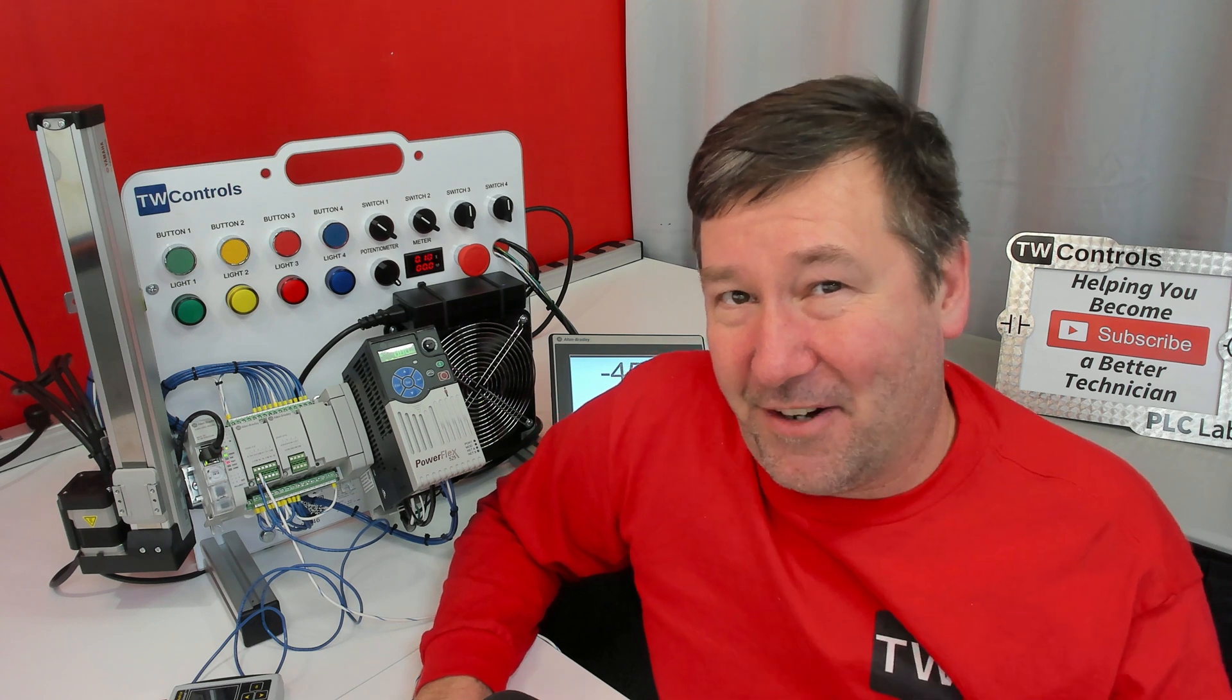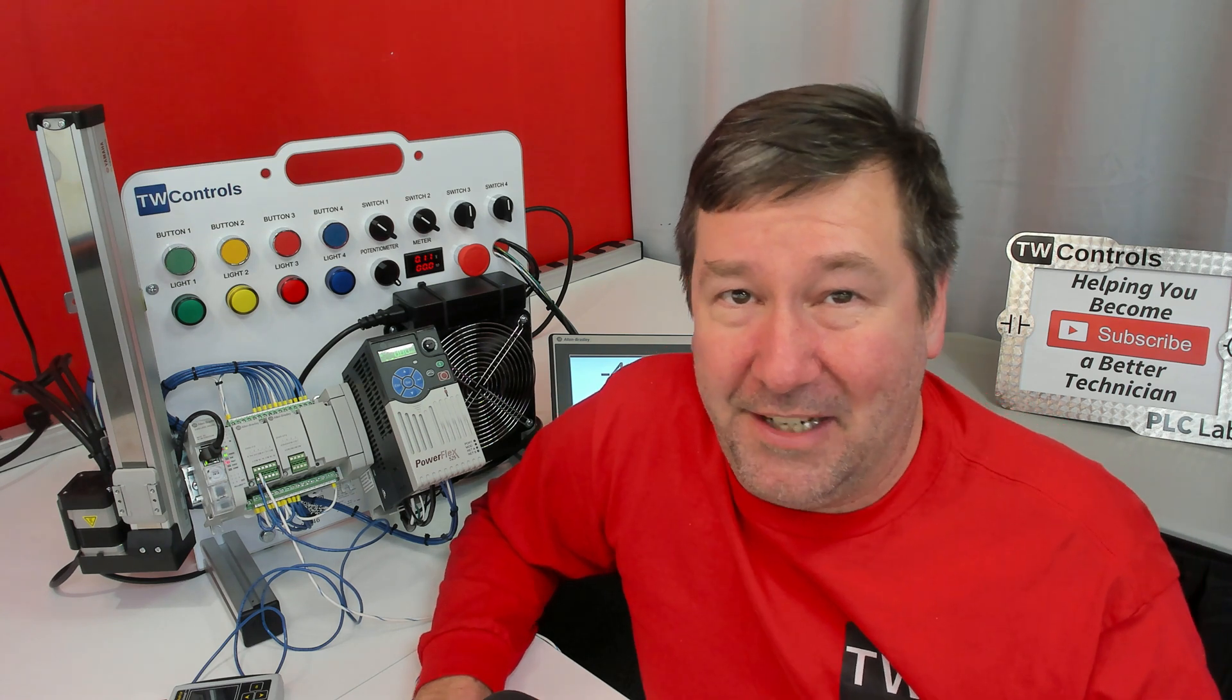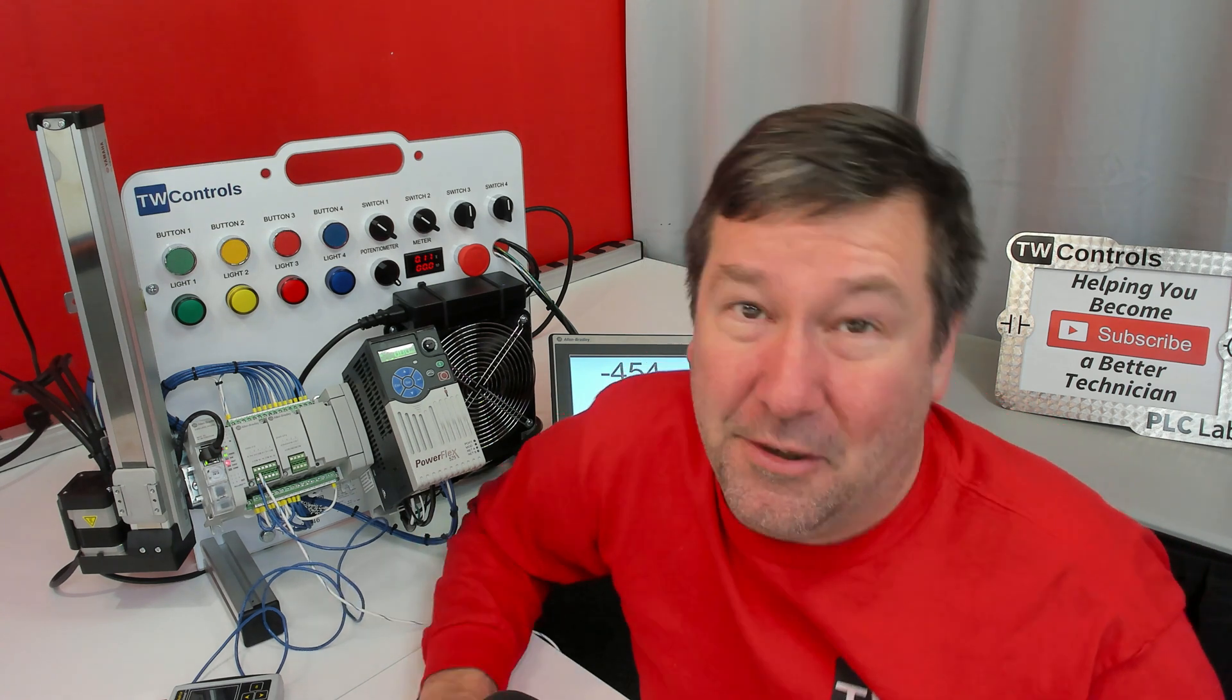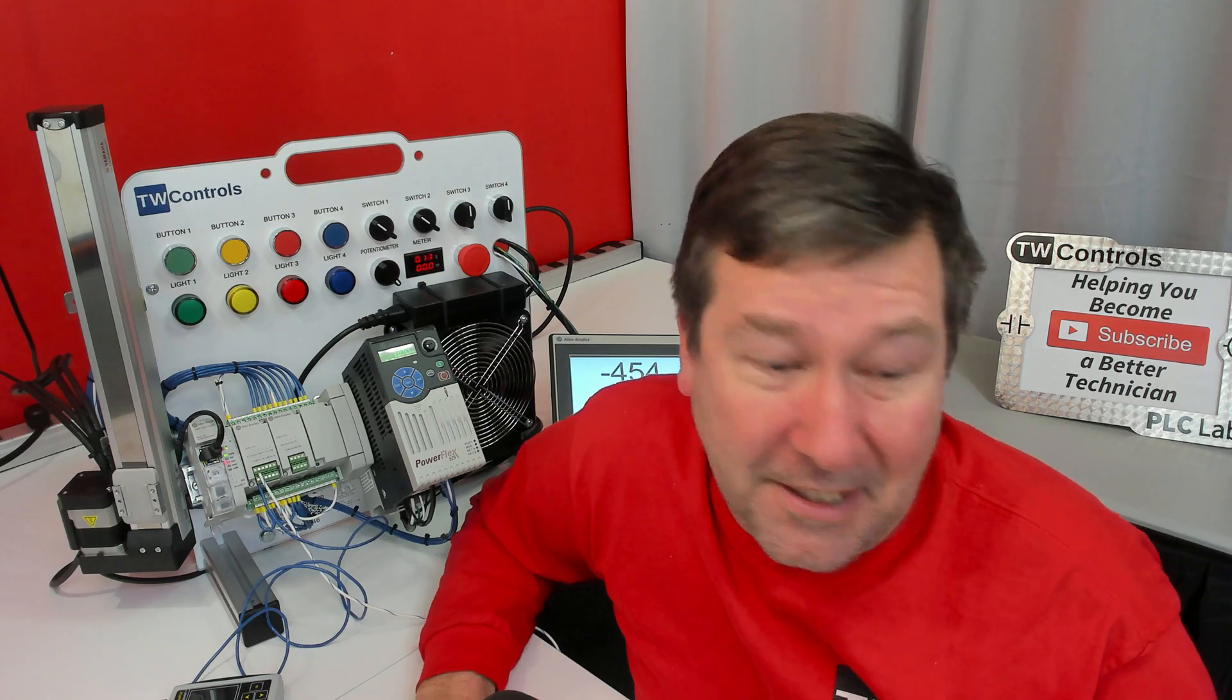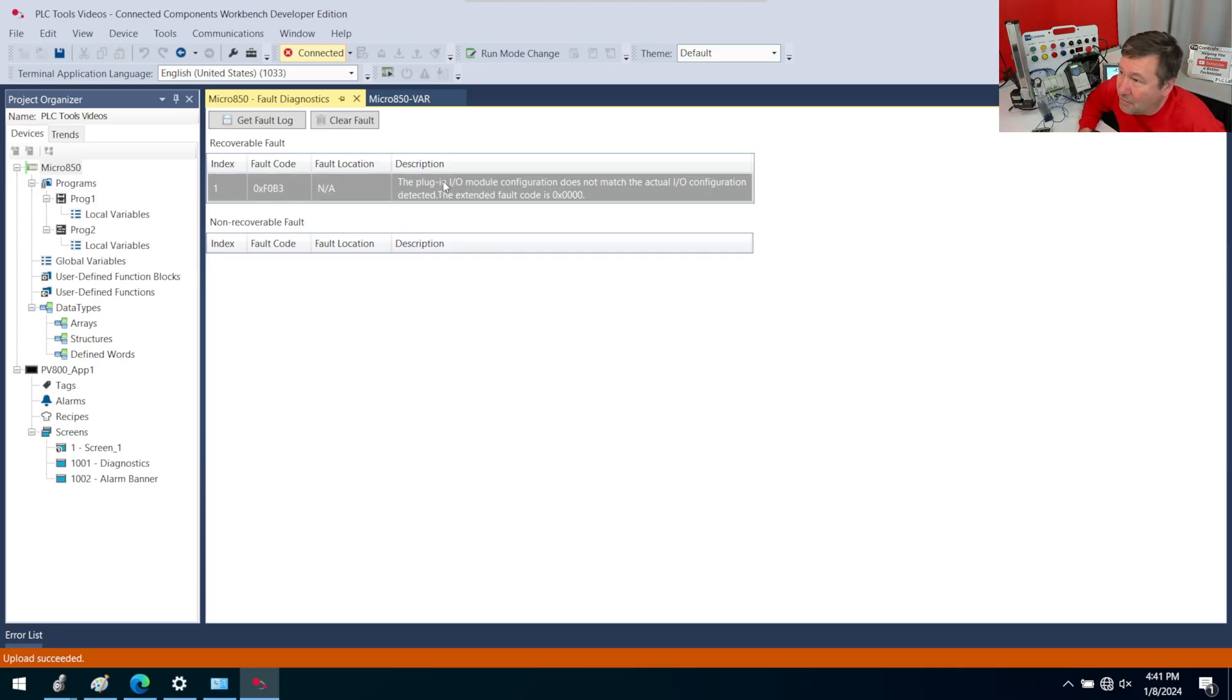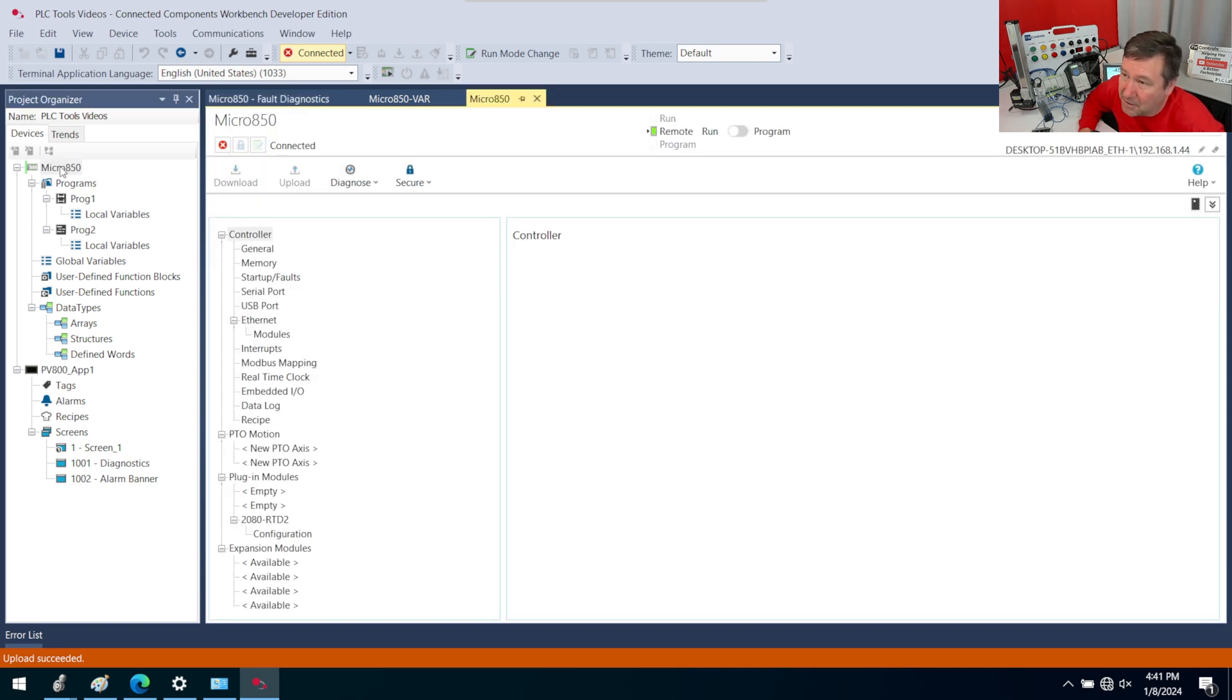Now, I'm going to be honest, I cannot figure out how to narrow down this fault. And that's why I'm going to go ahead and post this video because I hope you can help me out in the comments. But I would think at this point, I know I have an issue with a plugin IO module, and so I would want to go to my IO configuration, which I'll get to by double-clicking on the Micro 850.